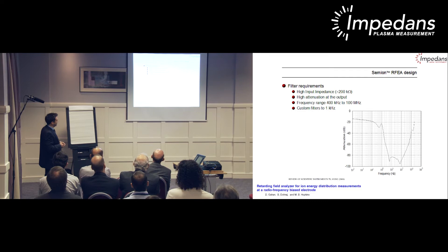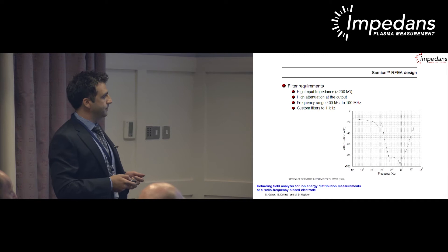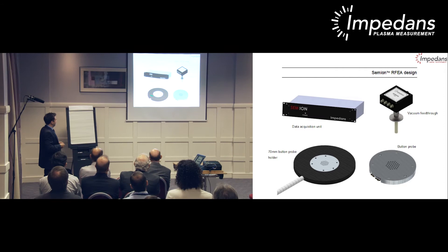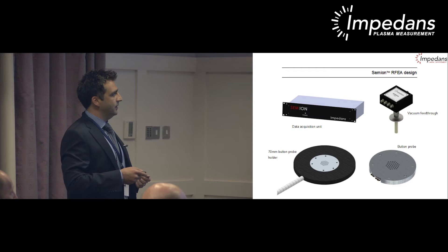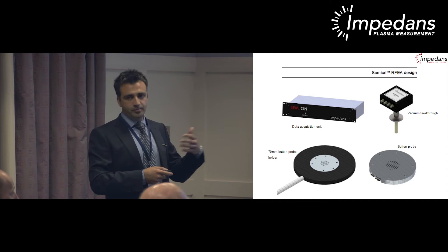Detailed information on the filtering has been published. The impedance needs to be quite high—typically greater than 200 kilo-ohms—so as not to disturb the RF bias. High attenuation at the filter output protects the electronics, with greater than 60 dB attenuation over the 400 kilohertz to 100 megahertz range, typical for RF applications. This can be pushed down to 1 kilohertz for pulse DC industry applications. The system consists of the probe holder, a replaceable sensing element, signal cable to a vacuum feedthrough, and a box of electronics to apply potentials and record ion current.